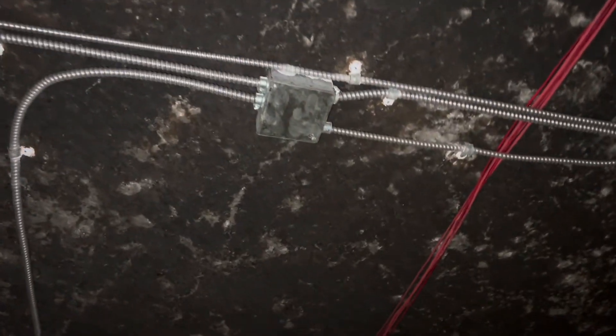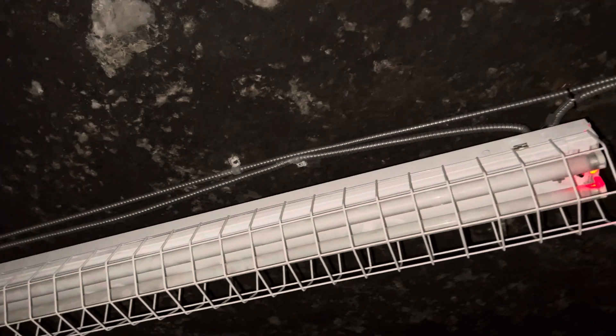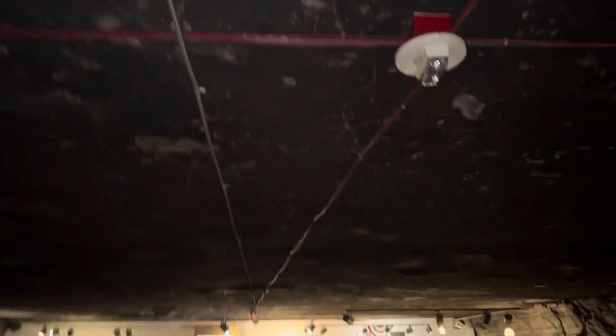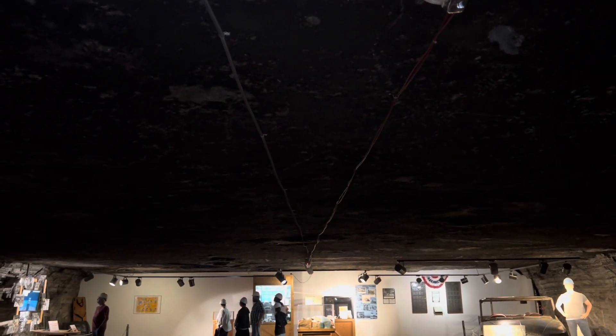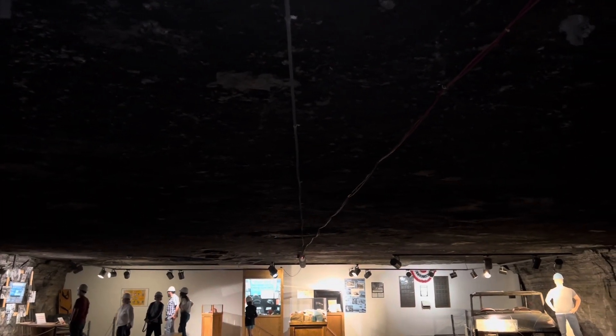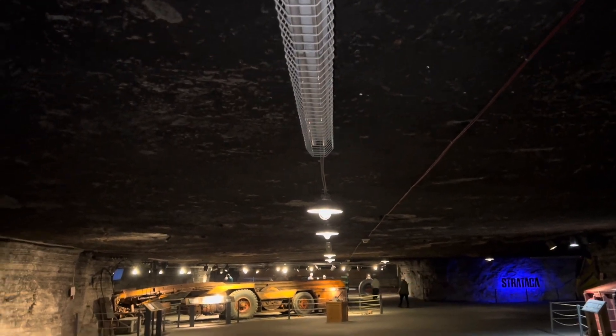Everything was shot with some shots. These ones look like they're covered so they don't rust or something, but they do look like there are some powder-actuated shots. Most of the stuff looks nice and straight going down here. Some things go into a weird angle, but the stuff is nice in a straight row right there. Got your fire alarm intersecting right there, got your MC, and everyone knows that MC is pretty hard to keep straight, so they did a good job on that.